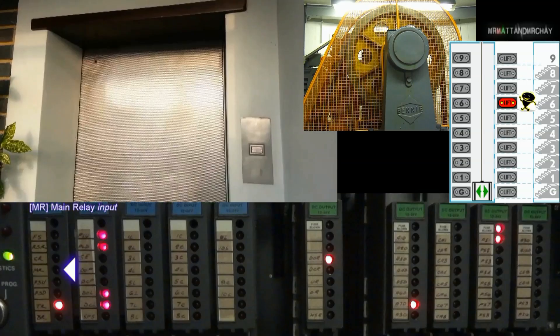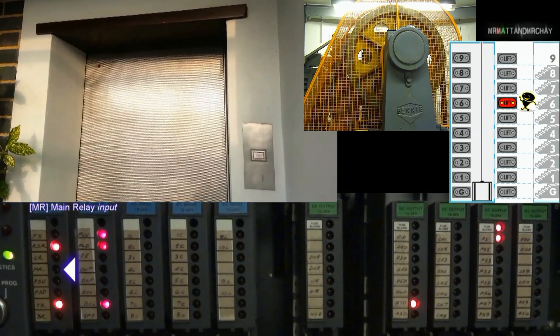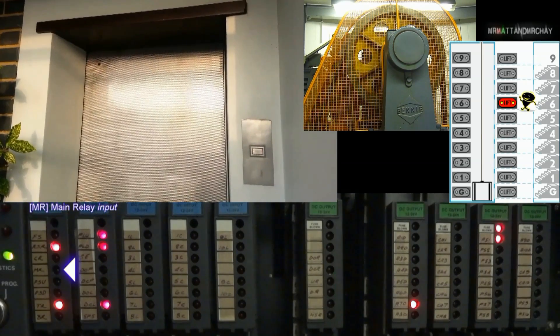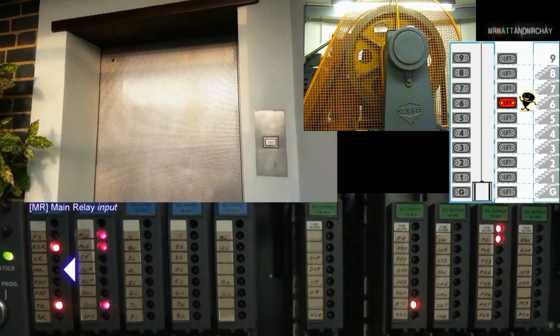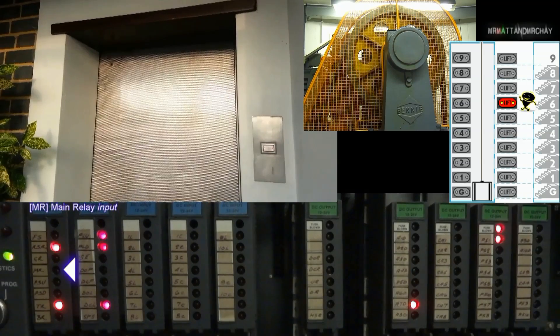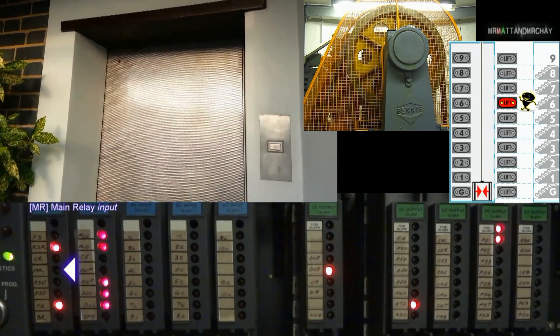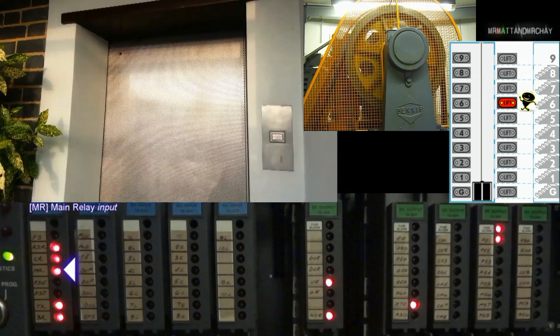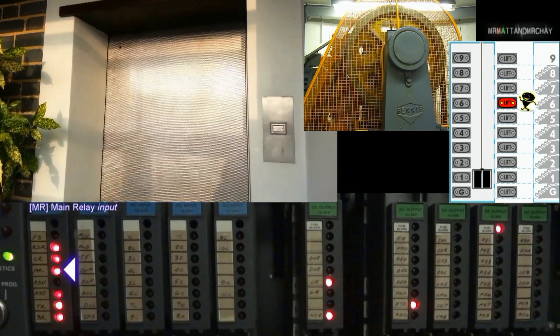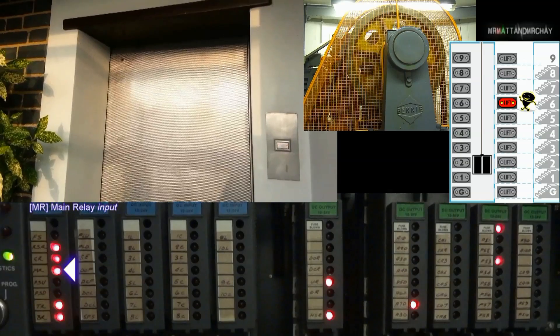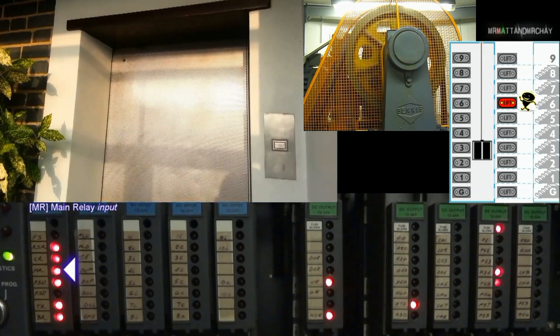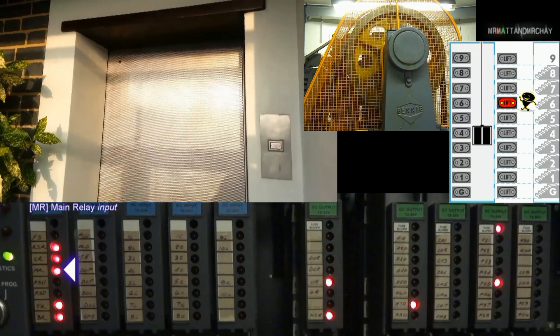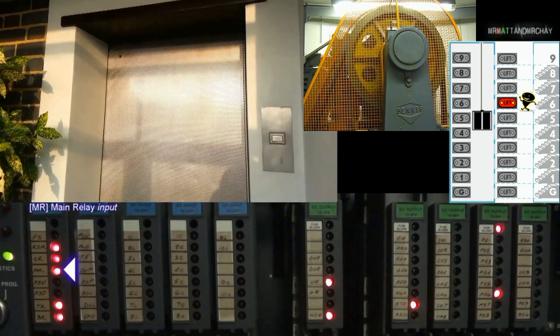MR, main relay input. The lift cannot run unless two relays are active. It needs an up or down relay and a main relay. The main relay acts as a safety, so that if the up or down relay were to malfunction and activate alone, the lift would not travel until the main relay is also on. As this is an input, I'm assuming that the controller needs to know whether the main relay is on or not. If the controller tries to move the lift up or down, and the MR input didn't activate, then the controller would know that the lift isn't moving and may reopen the doors. I'm not 100% sure.